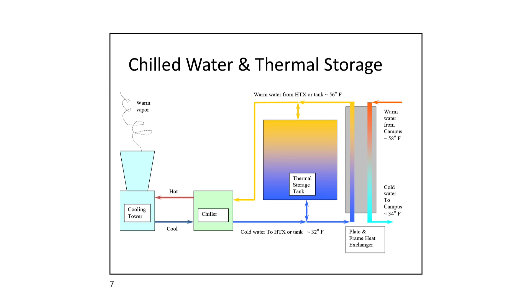And on the bad day, the chiller fails or the cooling tower fails. What it means is that the operators, instead of scrambling because the researcher's calling saying their laser failed, can very thoughtfully turn up the pump and just pump water out of the tank. So by having some kind of capacitance, some kind of storage, I avoid the crisis being cascaded down to my campus customers.